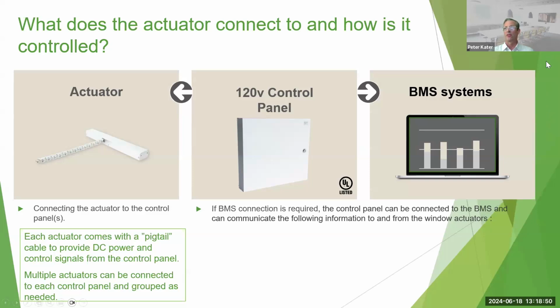And then thirdly, there's a connection between the controller and the building management system, if that's available. Now this allows the building management system to read information about window positions and so forth when the natural ventilation system is operating. It also enables commands from the BMS to be sent to the window control panel to customize its operation. The typical communication protocol between a BMS and a window controller is a BACnet IP data communication protocol. An alternative is KNX, but mostly it's BACnet in North America.